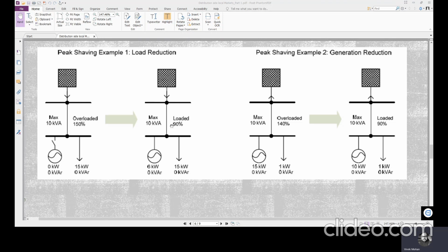So in the second case, what happens is we are slowly connecting this local generator into the system, and we are stepping up the generation from 0 to 6 kilowatts. So out of this 15, 6 is locally fed. Now remaining is 9. So 9 comes from the upstream grid, right? So now it's only 90% loaded. So if there is a 10% tolerance for this line flow limit, then that is satisfied now. It is only 90% loaded.